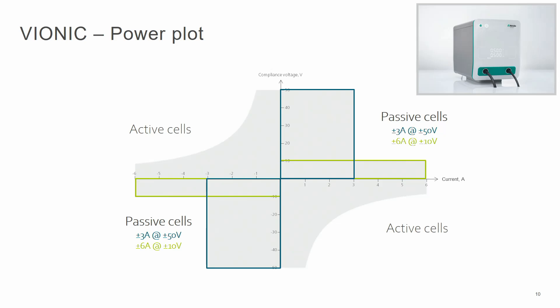The potentiostat Vionic can be set in two different operating modes. The first, framed in green, is the most common used operation mode because most electrochemical experiments can be performed with it. The maximum operation point is plus 10V compliance voltage at a maximum current of 6A. The second operating mode, framed in dark blue, is the high compliance mode, used when a compliance voltage above 10V is needed. The maximum operation point is plus 50V compliance voltage at a maximum current of 3A. This is sufficient for demanding experiments in the field of organic electrosynthesis.